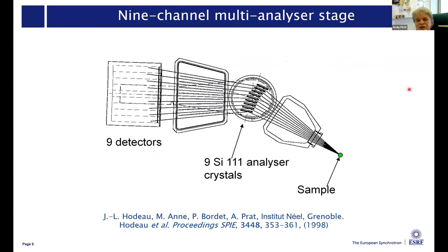Talking about multi-analyzer stages - this is the heart of one of the key components that makes ID22 a high resolution powder diffractometer. This was conceived right at the beginning for BM16 by Jean-Louis Hodeau, Michel Anne, Pierre Bordet and Alain Prat at the local CNRS Institut Néel. It means you put nine crystals in parallel with scintillation counters behind them. The radiation scattered from the sample has to fulfill the Bragg condition on a crystal before it can go into the detector. Putting nine together gives you nine times the counting efficiency.